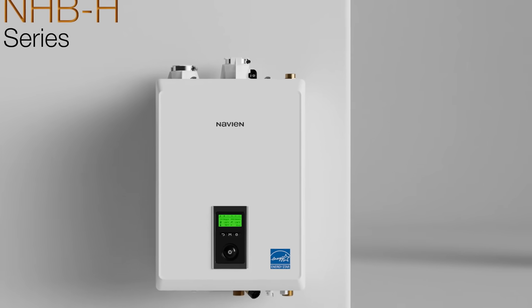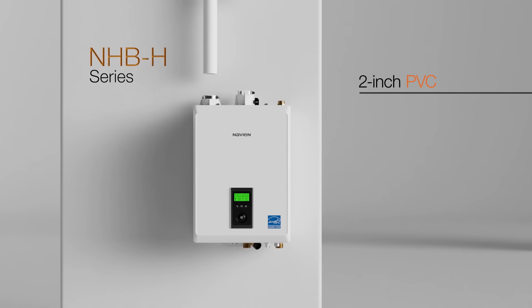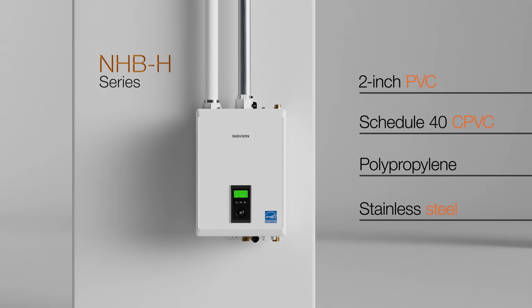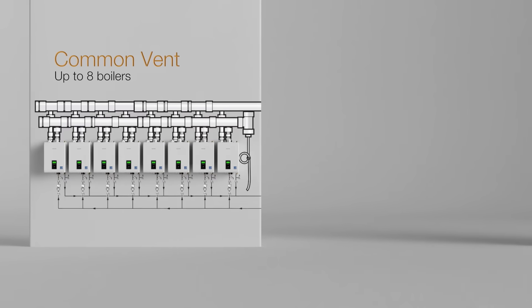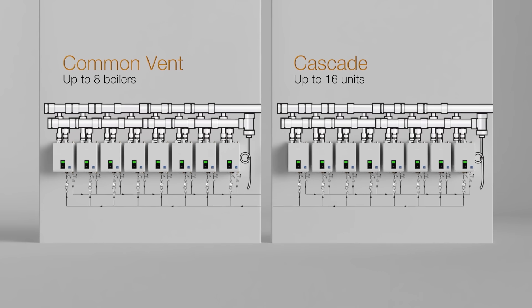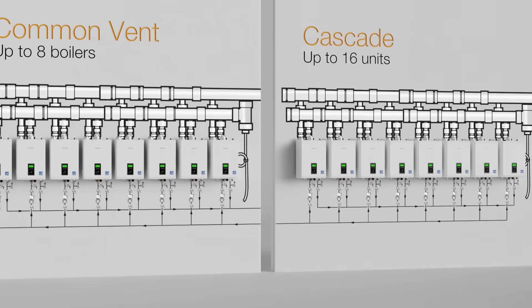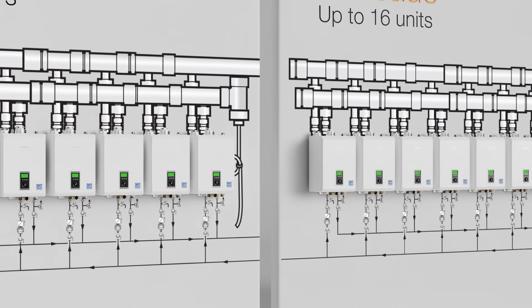The low exhaust temperatures of the condensing NHB-H allow use of either 2-inch PVC, Schedule 40 CPVC, polypropylene, or stainless steel up to 65 feet, and up to 150 feet for 3-inch. Installers can common vent up to 8 units and cascade up to 16 units when using the NHB-110H or NHB-150H for greater capacity, reduced venting terminations, and increased turn-down ratios.